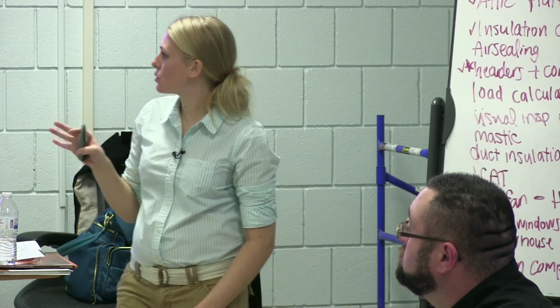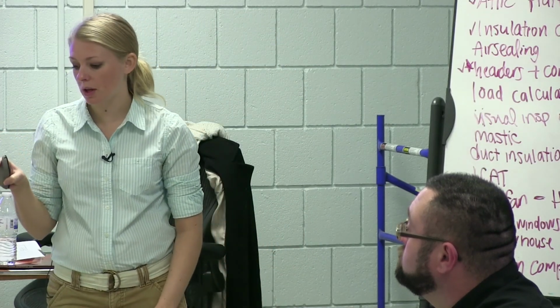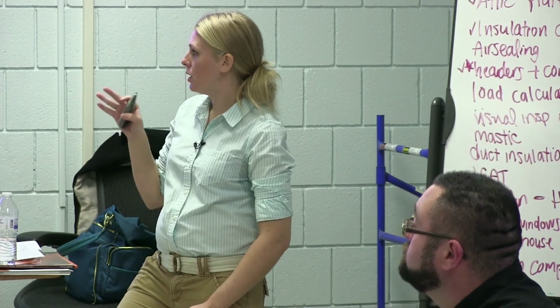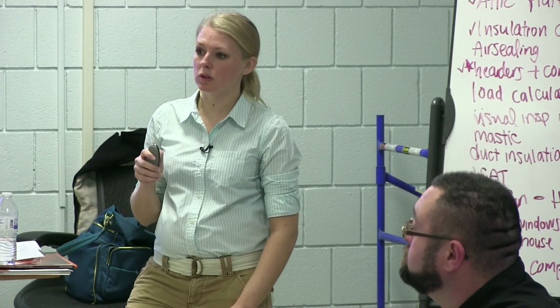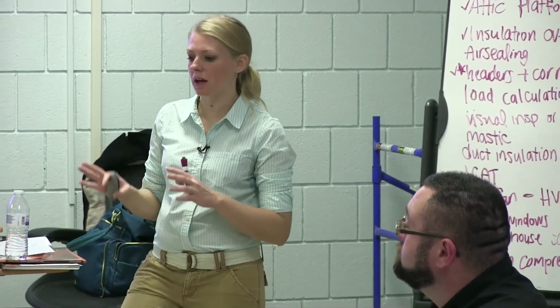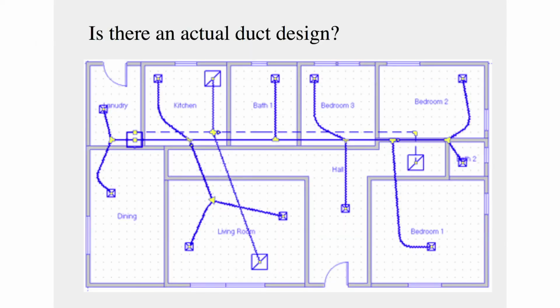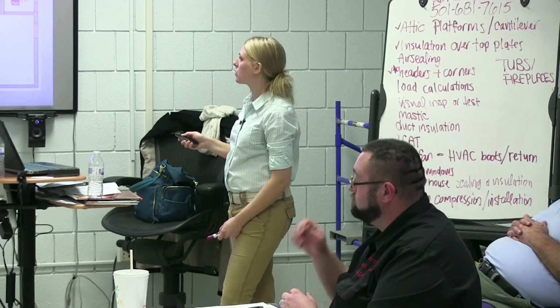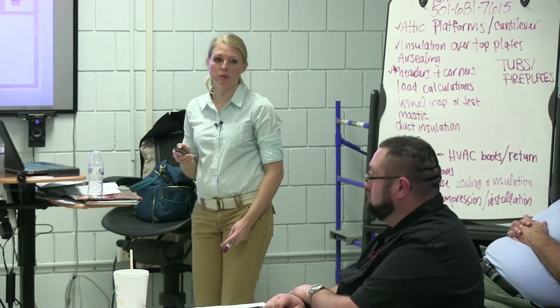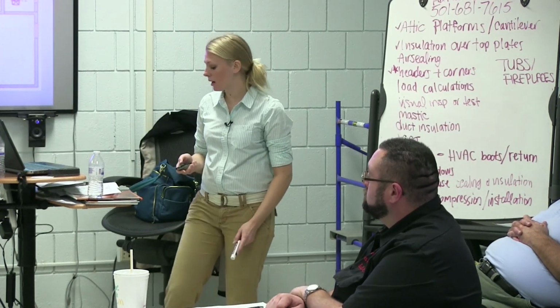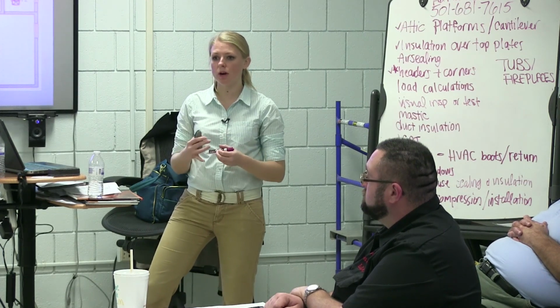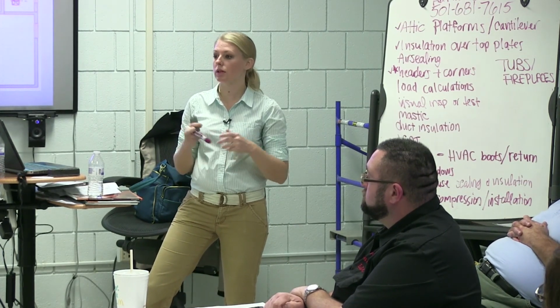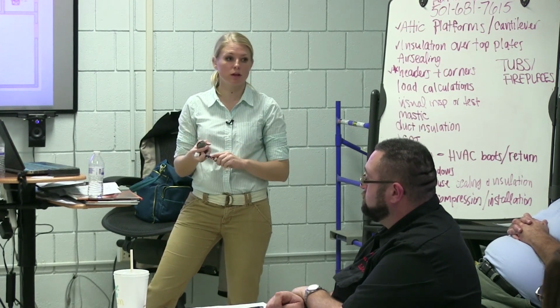So this is one thing that can potentially come out of a Manual D, which is you see now what that duct system looks like. Now, whether or not this is a good duct design, I'm not saying that. I'm just saying this is one of the things that gets produced. And then there's another chart that goes along with it that will tell you exactly what the CFM is coming out of this duct, and what size this duct is that needs to be installed. So in a certain way, it's kind of nice, because if everything's done correctly, it can give you a list of exactly what you need to purchase as far as your duct system goes.